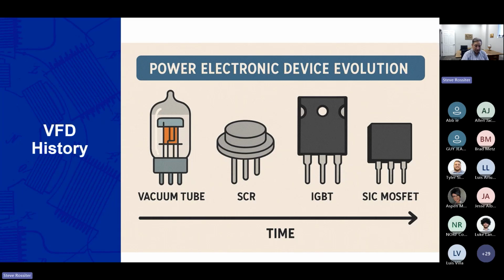And that was, like I said, originally a patent of NOLA. Well, that company, Vectrol, after a few short years, was acquired by Westinghouse. And as Luke said, I was privileged to be the commissioning agent for serial number 3 of the Westinghouse Accutrol 300 drive, which was based on the next generation of an SCR. They called it a GTO, a gate turnoff thyristor, which is the same as a thyristor, same as an SCR, except it had a gate where you had these big drivers, so you had to use current to actually stop the flow of current. And that allowed you to get some control at low frequencies, talking about maybe a kilohertz of switching frequency back then.